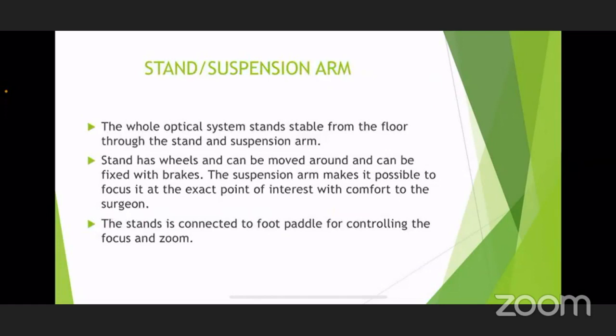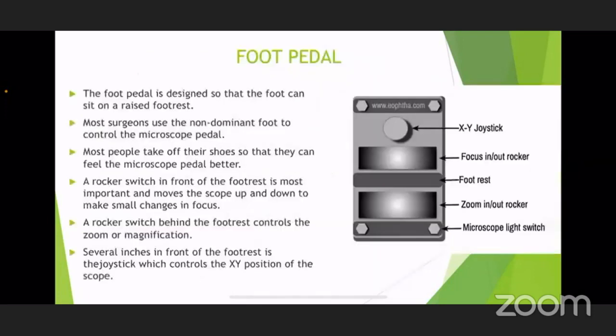The stand/suspension arm basically gives stability to the microscope. The foot pedal settings have a joystick which helps in moving in the horizontal plane, allowing fine movements. There is also a footrest. This is all programmable — the upper rocker switch could be for focus in and out, and the lower rocker switch for zoom in and out, or we can have interchangeable settings depending on the surgeon's convenience.